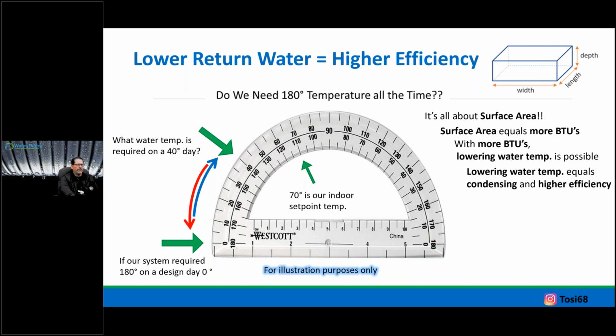But we had these devices, right? We had the ability to add them to even a cast iron boiler. So I was asking people, why do we need 180-degree water when it's a 40-degree day outside, right? Allowing something now to see the outdoor temperature. I agree, on a 0-degree day, we need 180. I get that if that's what the house needs. Again, we have a threshold with that piece of equipment. I'll say it again, 140. You don't want to go below that on returning water on a non-condensing piece of equipment because it will condense and now we short-life the equipment.